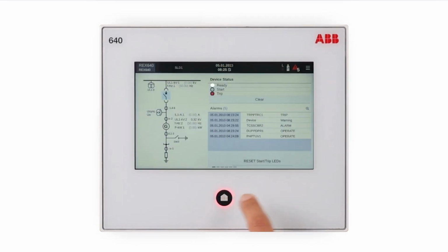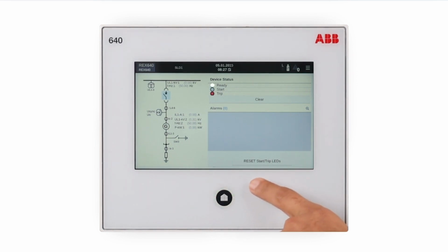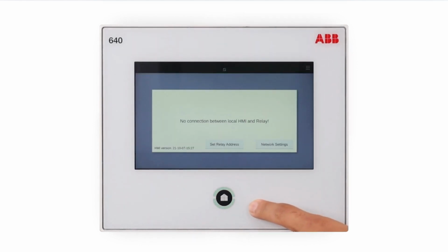The home button indicates the relay's status at a glance. In normal situations, the home button shows a steady green light. Any other situation that requires the operator's attention is indicated with a flashing light, a red light, or a combination of these. When the relay is set to test mode, the home button shows low frequency blinking green indication. The home button shows high frequency blinking green indication in case of communication loss between relay and LHMI, but no IRF, or LHMI not running normally or in startup initialization phase.